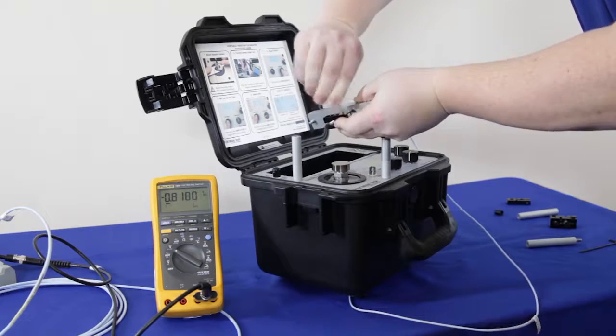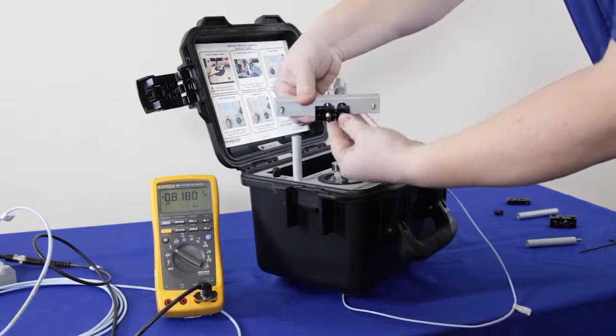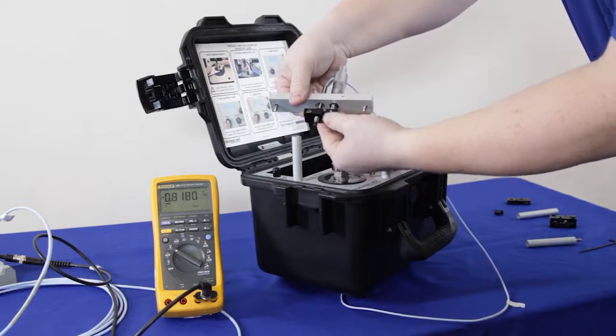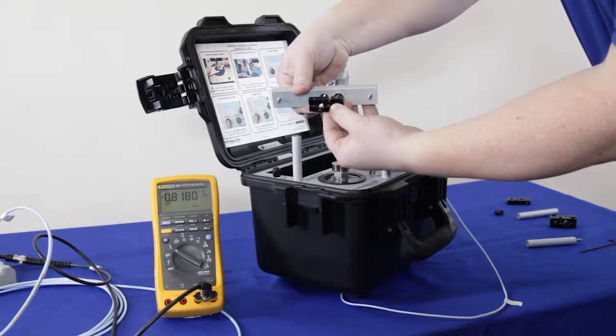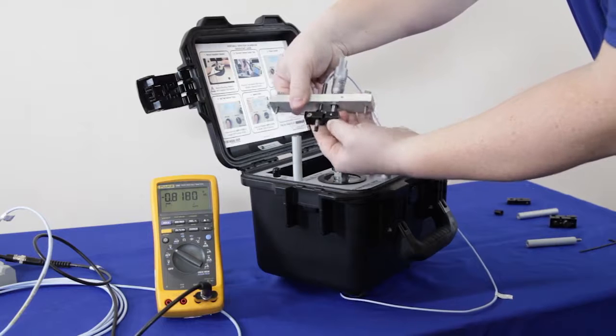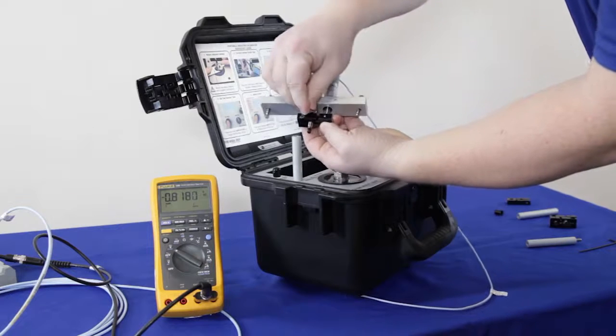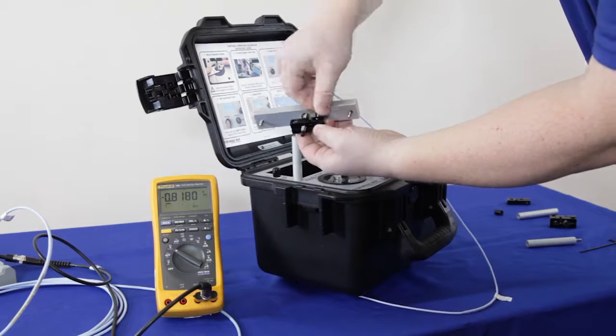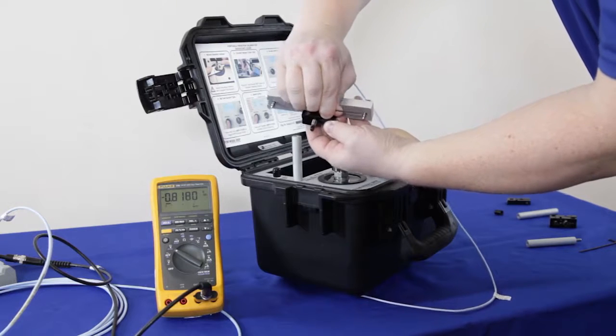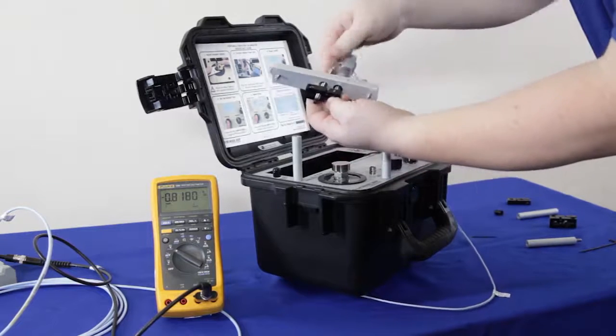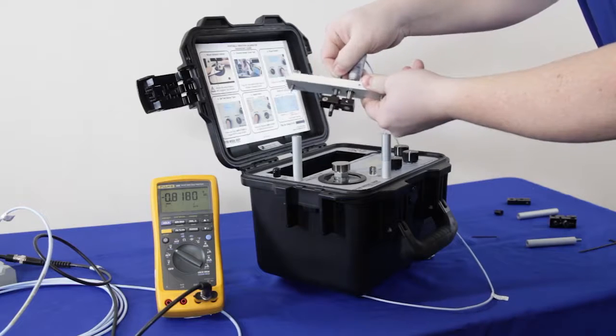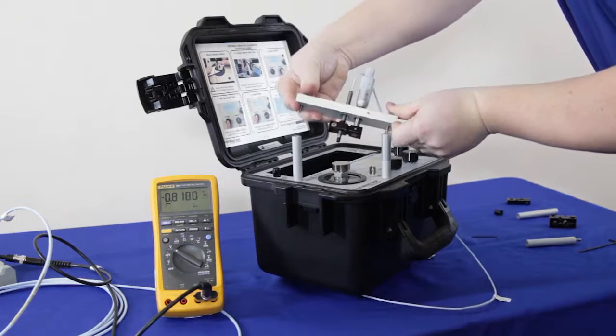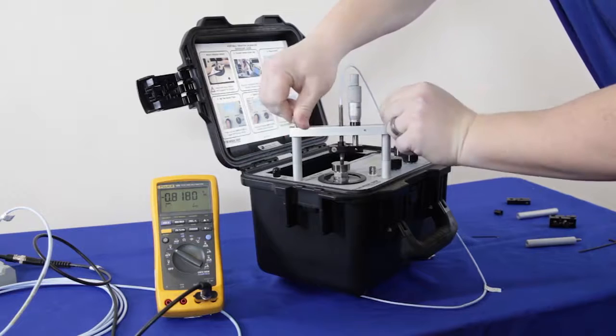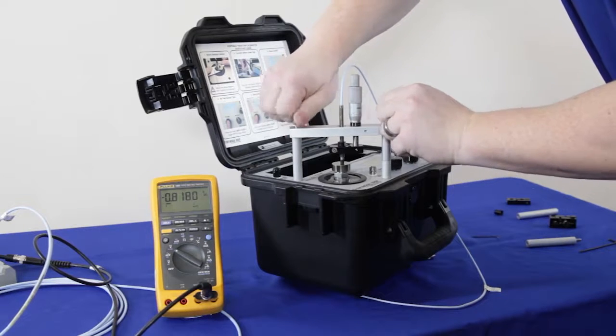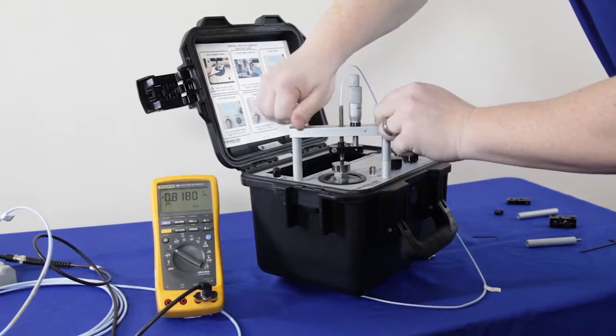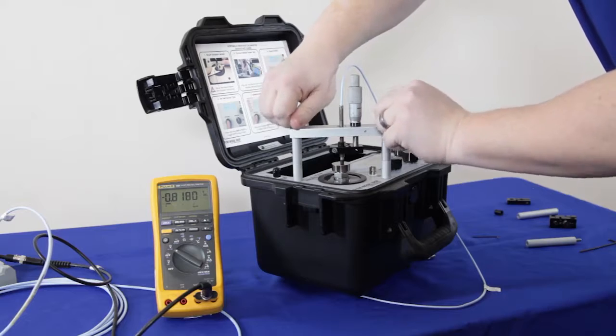So what I want to do is just loosen that screw a little bit, position my black bracket somewhere on the probe barrel. It really doesn't matter for the purposes of doing a dynamic test. And once I feel comfortable with it, go ahead and tighten that down with the smaller wrench. And now the hard part is complete. This can't move within the assembly. I can go ahead and mount it to the top of the columns. Tighten that down. And we're almost ready to test.